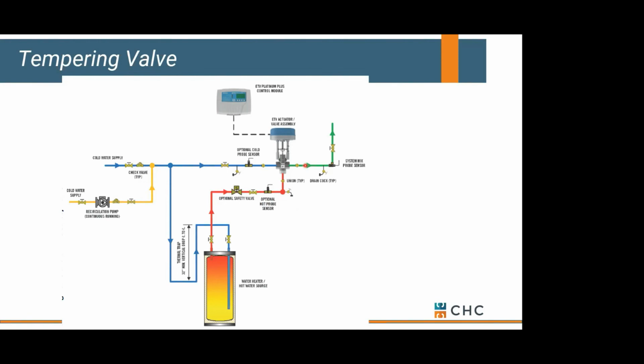My only caution here is we've seen a lot of individuals take this recirc pump and tie it directly into their water heater, into this leg here, and then have a check valve above it, basically. The recirc has to be able to serve both sides of this master mixing valve. So you have to be able to have access to the cold port as well as the hot port. So just keep that in mind. Otherwise, we end up with some cold legs and some long waits for hot water in the morning. All right, that's our master mixing valve.